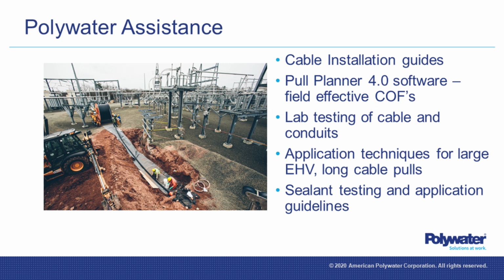Absolutely. Would you agree with that? Yeah, I do. There are some differences when you look at a city underground in the streets versus distribution going into neighborhoods. Cable manufacturers can help you plan on load. The calculations let you look at what-if situations, like if you're installing 3 500s today but your city will scale up to need 750 or 1 million kcmil in those conduits. To reduce costs, you could look at installing larger or multiple conduits in those areas. You also want to consider DERs and how that affects the grid, whether they need a place to go. So it's really by design or by demand.